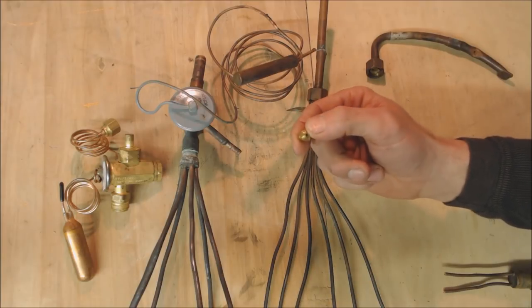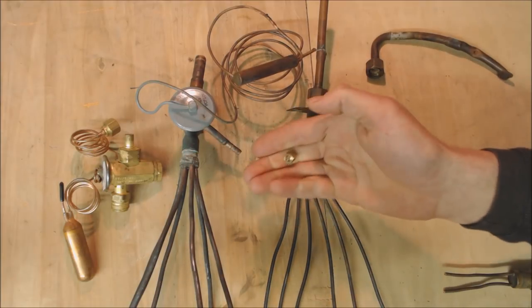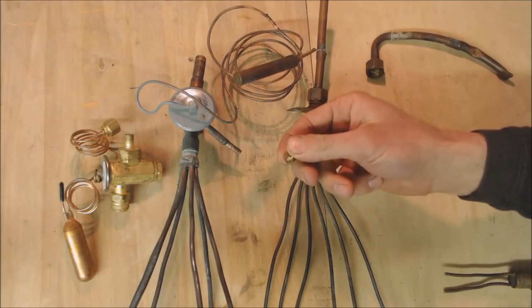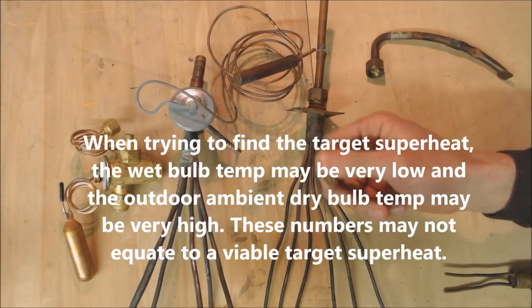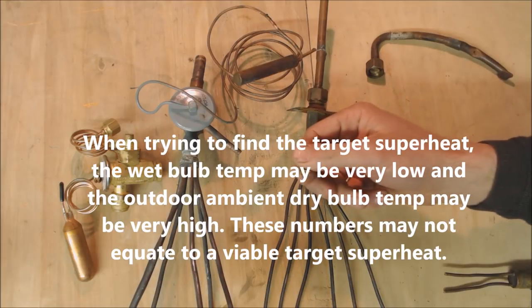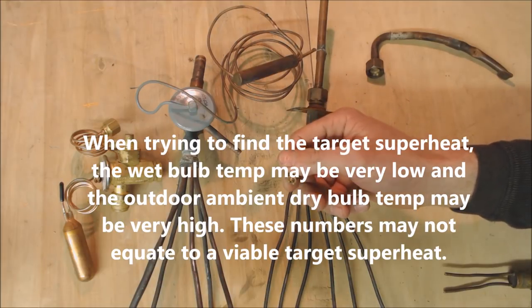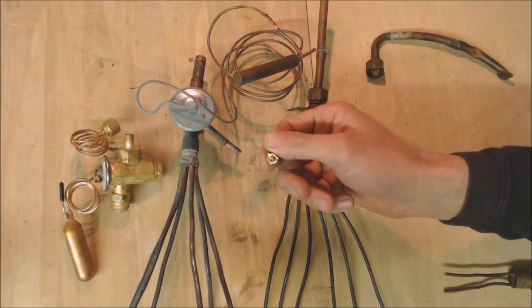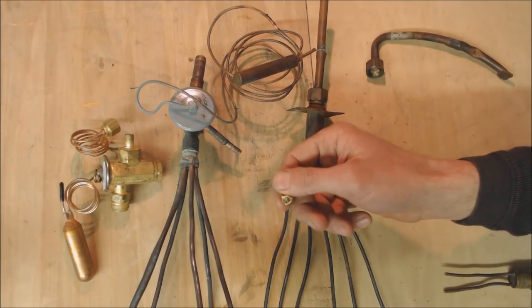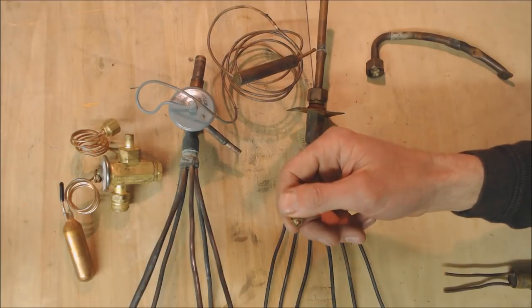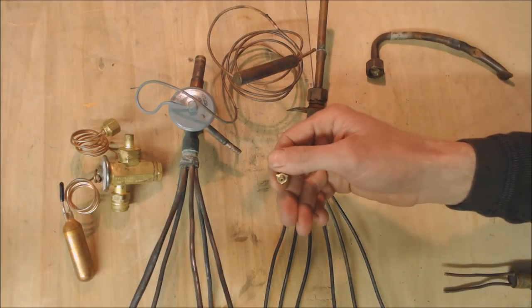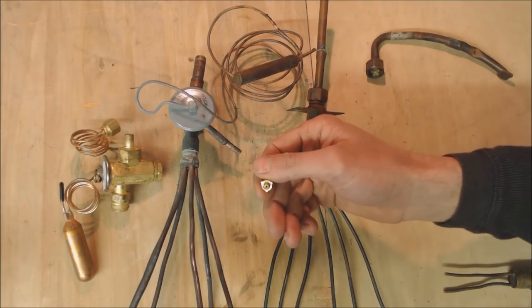These are a fairly cheap alternative to TXVs. But these are not very good for dry climates because you have to set the superheat a little higher. This is just a fixed orifice and it's not able to adjust the refrigerant flow. When you want the efficiency of the system to be the best, like when it's really hot, it's actually at its worst with a piston.